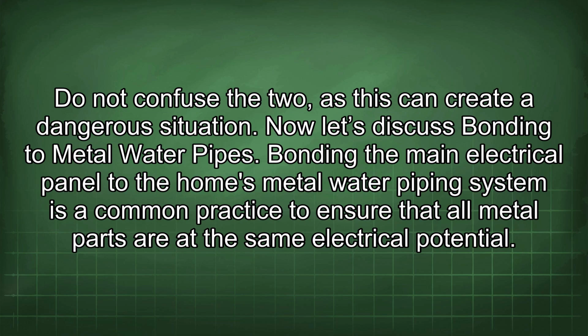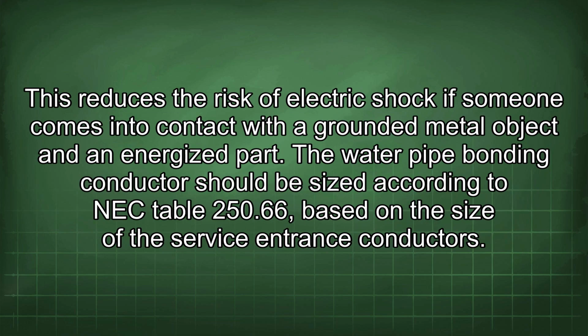Now let's discuss bonding to metal water pipes. Bonding the main electrical panel to the home's metal water piping system is a common practice to ensure that all metal parts are at the same electrical potential. This reduces the risk of electric shock if someone comes into contact with a grounded metal object and an energized part. The water pipe bonding conductor should be sized according to NEC Table 250.66, based on the size of the service entrance conductors.